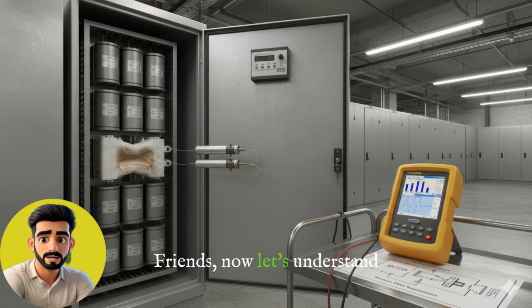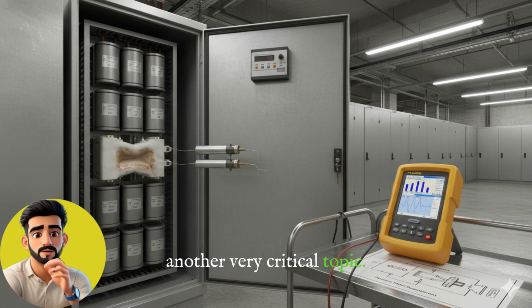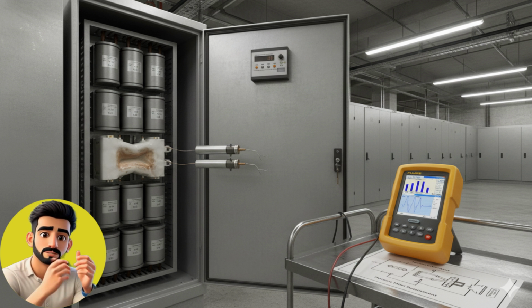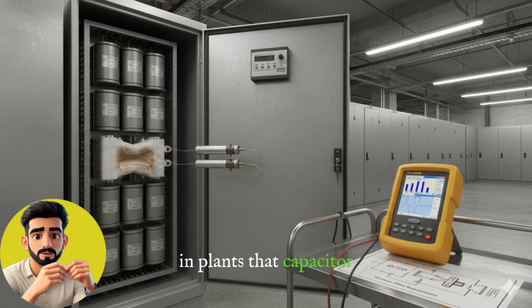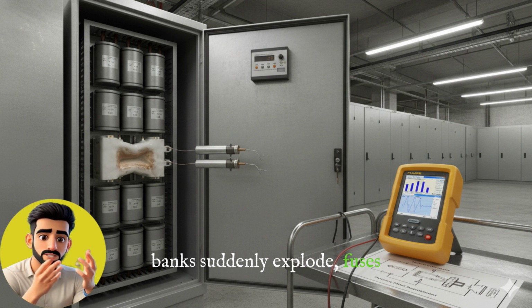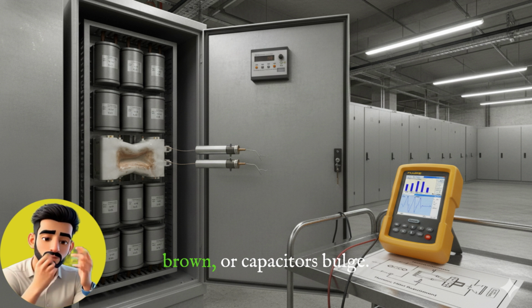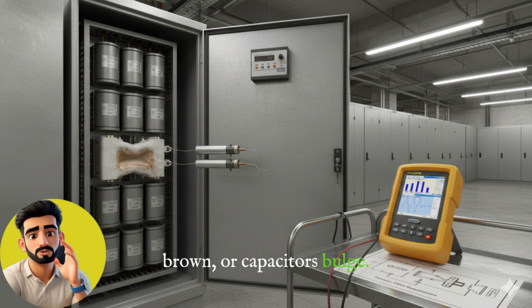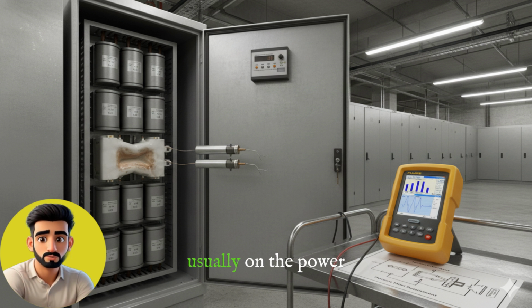Friends, now let's understand another very critical topic. Why do capacitor banks fail along with harmonics? You might have seen in plants that capacitor banks suddenly explode, fuses melt, cans turn brown, or capacitors bulge. The first blame is usually on the power factor controller. But the real problem lies in harmonics.